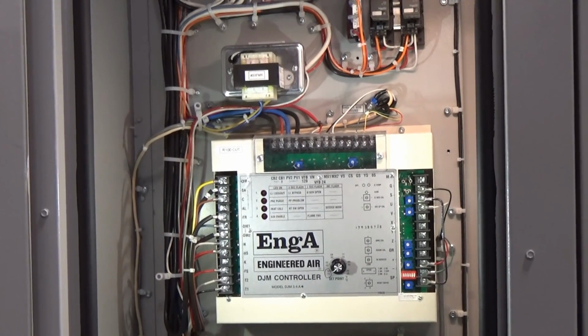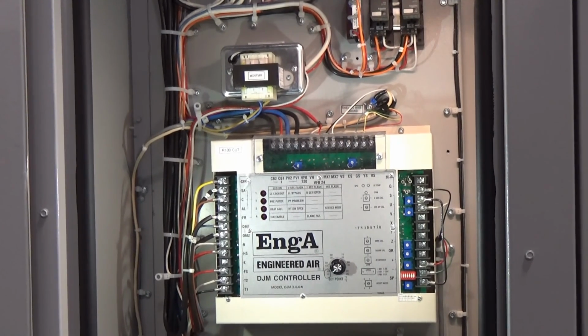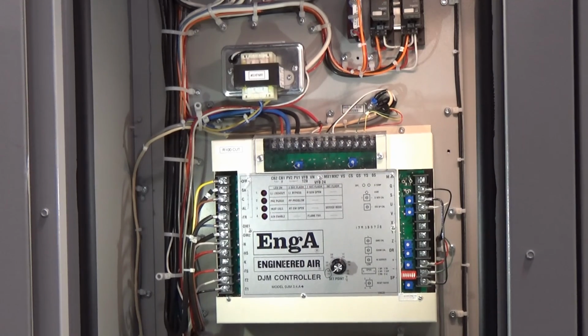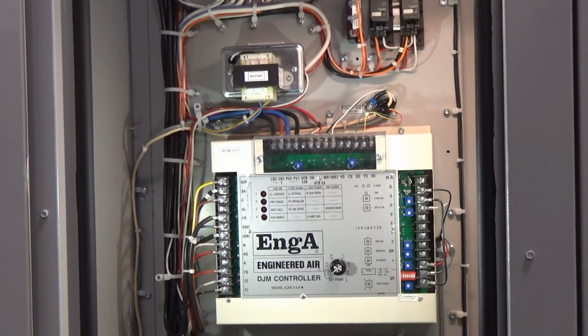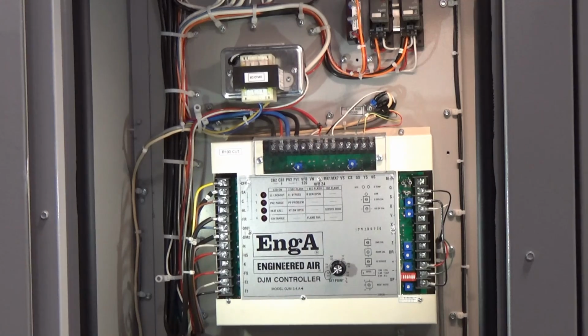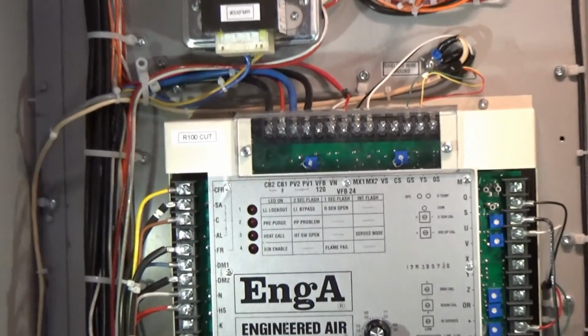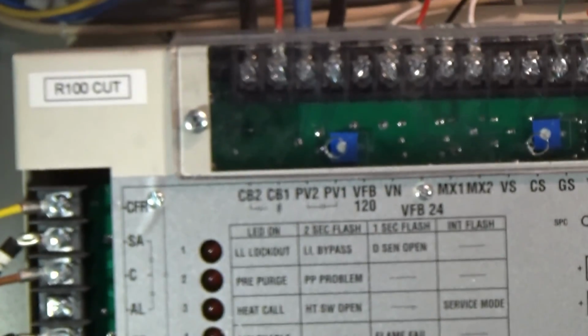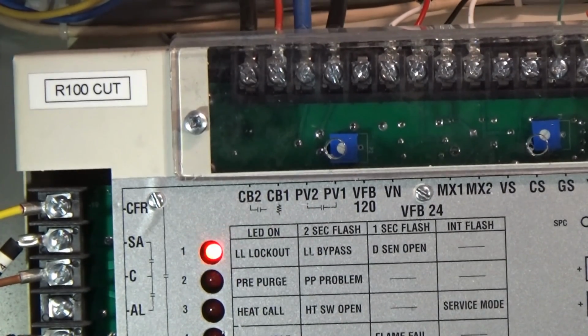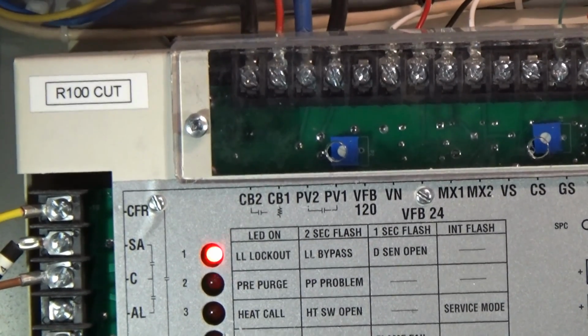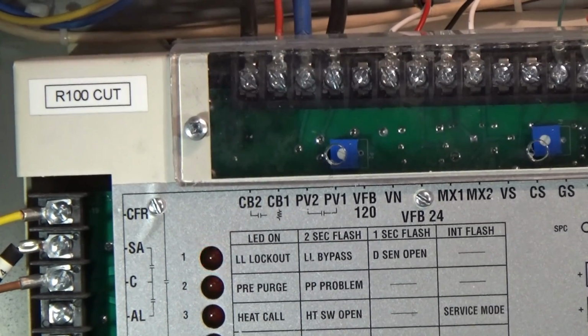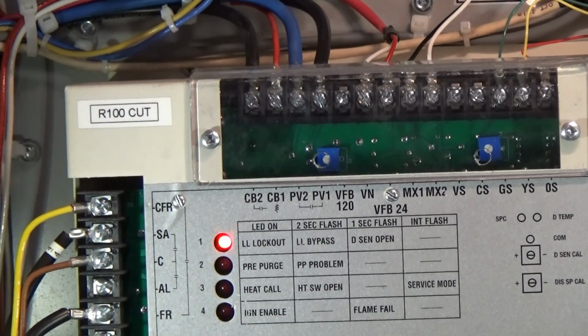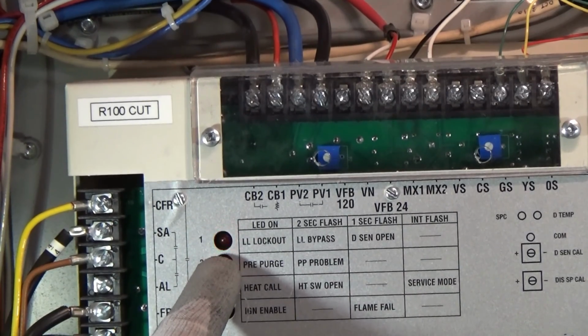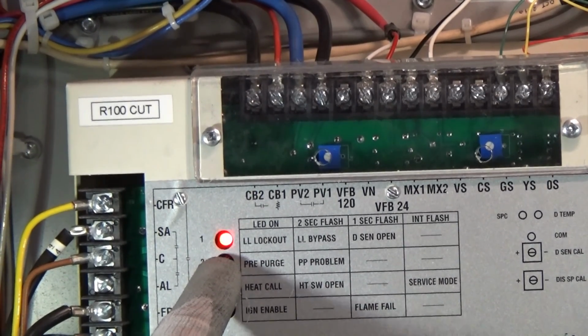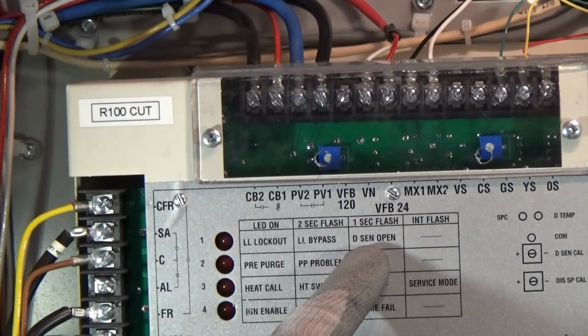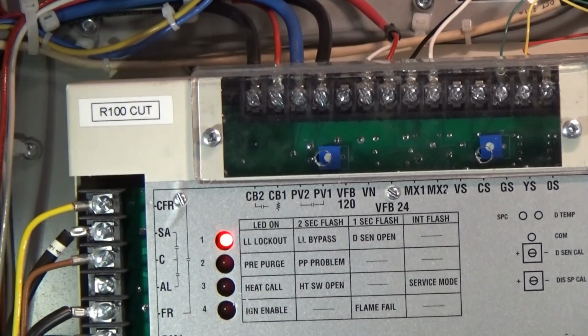The discharge air sensor is based on resistance. A reading of less than 880 ohms will show up as a low limit alarm. A resistance greater than 4,000 ohms will show up as an open sensor alarm on the DJM 3.4 board. With a faulty discharge air sensor, there will be a 1-second flash on the DJM board. This will indicate that your discharge air sensor is open. This sensor will have to be replaced.